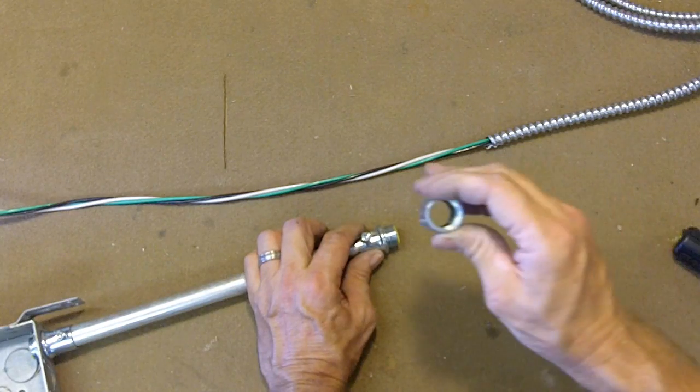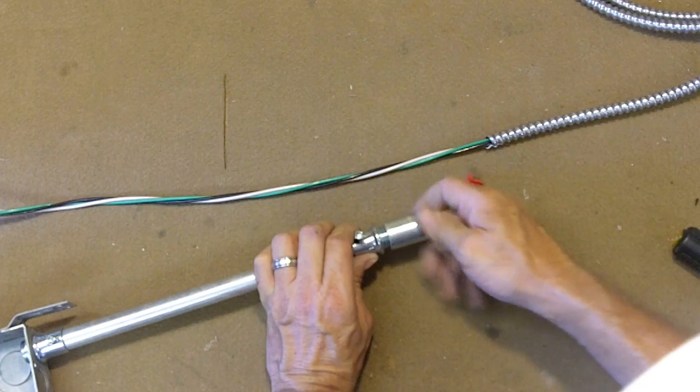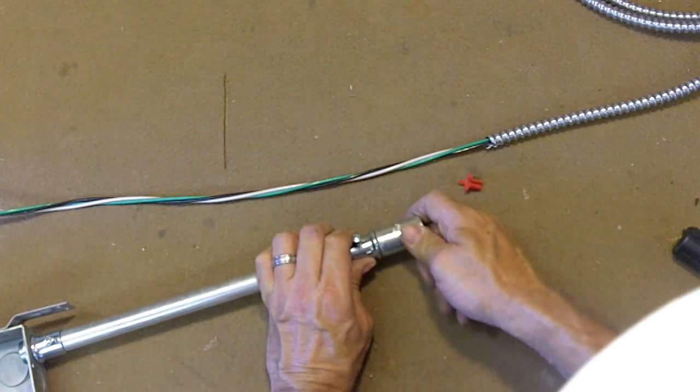And then we'll take a half inch GRC coupling, thread that onto the connector. And we're not going to tighten it down yet and I'll show you why in just a second.